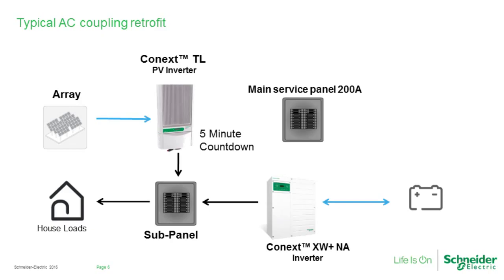So what we can see is that suddenly the grid's gone away. And we know that the grid's gone away because, well, it's not there anymore on the slide. But we have still, after a 5-minute countdown, that Conext PV inverter still pushing power out onto the sub panel. And it's doing so because the Conext XW Plus is actually creating that sine wave that's needed for the system. Now you notice here that there's still a bidirectional arrow on the right hand side pointing to the battery. So we're going to talk a little bit later about some of the charging characteristics that occur during an AC coupling retrofit.